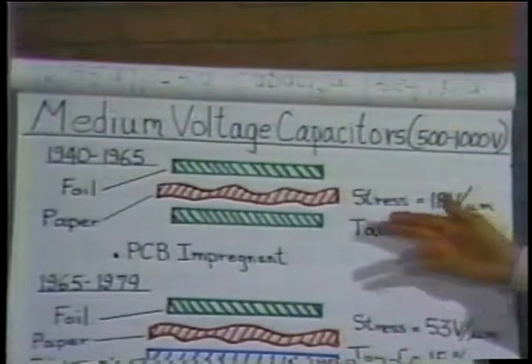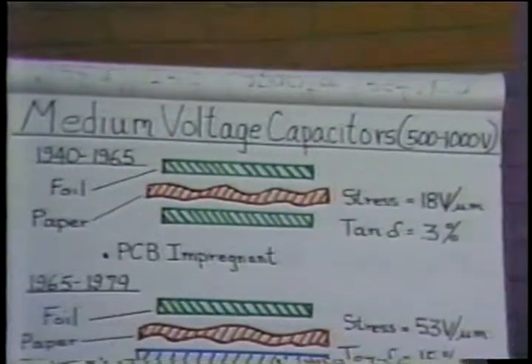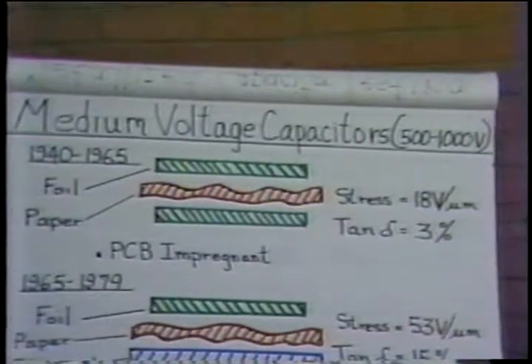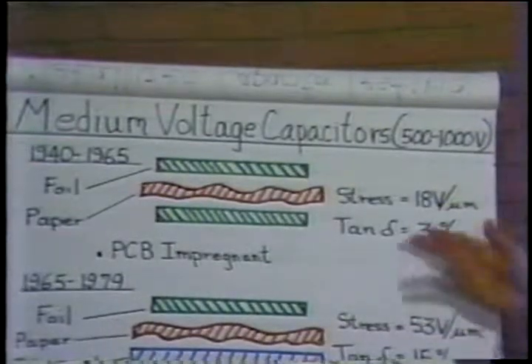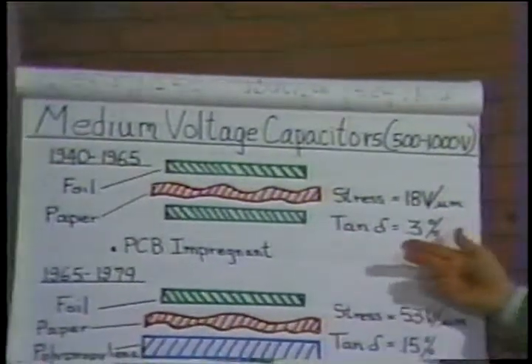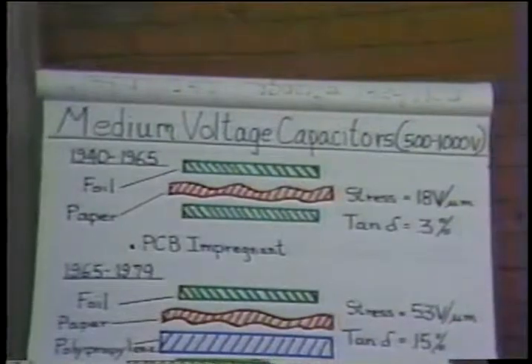I'd now like to take a look at the technologies, and changes of technology, in the medium voltage area. Again, for many years, the paper foil construction was the old standby. It was impregnated with a PCB fluid, and it was stressed, again, at 18 volts per micron, and had a high dissipation factor. Thermal runaway was a problem in this type of capacitor, as was dielectric puncture. The paper was fairly porous.